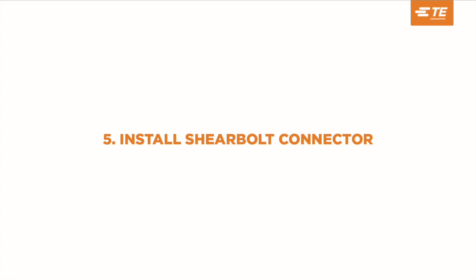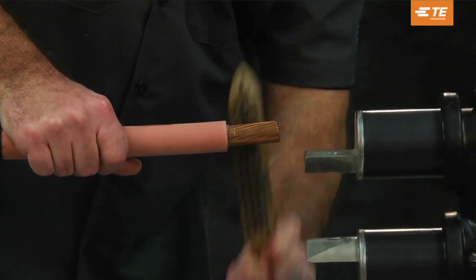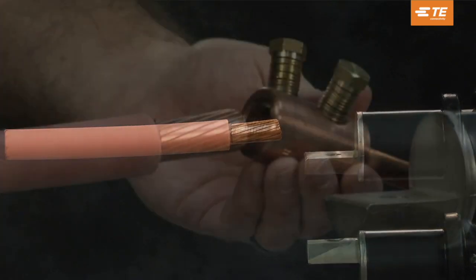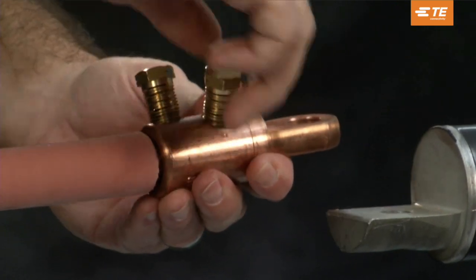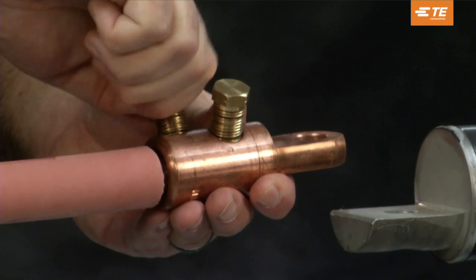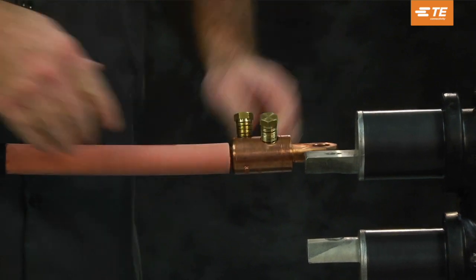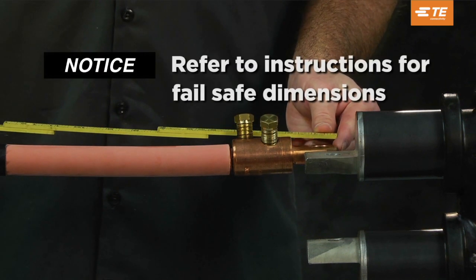Install the shear bolt connector. Using a wire brush dedicated for use on aluminum or copper conductors, thoroughly clean the bare surface strands of the conductor end. Cleaned conductor ends should be installed immediately after wire brushing to prevent reformation of oxides on aluminum conductors. Insert conductors so that the insulation butts up with the end of the connector. Hand tighten the shear bolts so that the connector stays in place. Verify the dimensions between the end of the lug and the semi-con cutbacks.